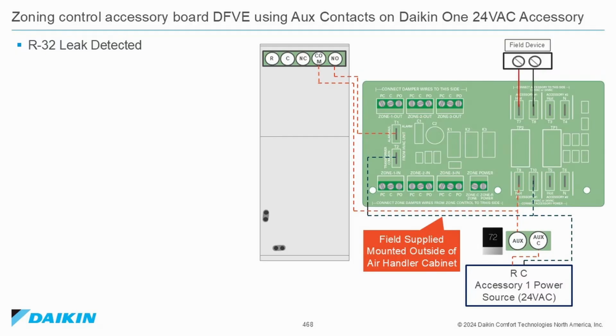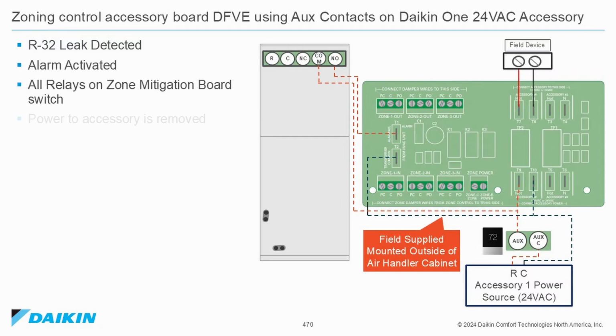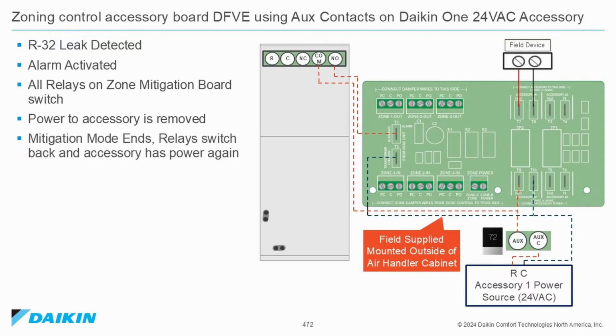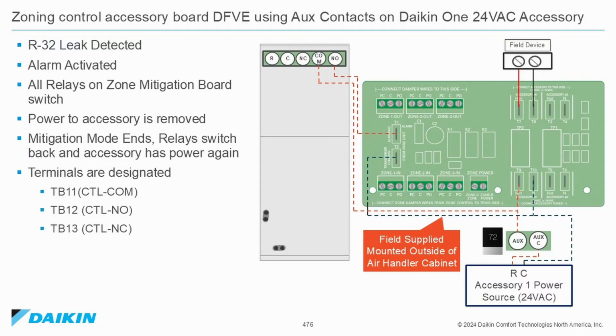Zoning control accessory board DFVE using auxiliary contacts on Daikin One 24 volt accessory. R32 leak detected. Alarm activated. All relays on zone mitigation board switch. Power to accessories is removed. Mitigation mode ends, relay switch back, and accessory has power again. Terminals are designated TB11, control common, TB12, control normally open, TB13 control normally closed. The wiring that you're seeing is field supplied outside of the air handler cabinet.